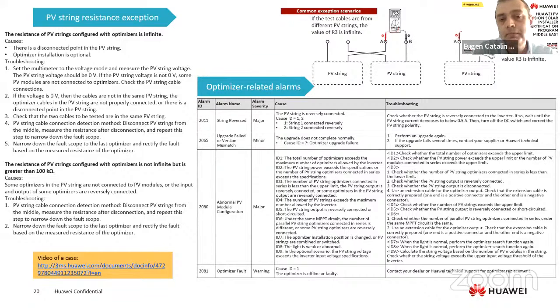We will probably have some upgrade failed alarm, for example. Why is this happening? Sometimes it happens because you set up the inverter in the evening, almost night, when the DC is low, even though the inverter starts the update. It starts because it has power from AC. It will upload the firmware to 80%, and after that, between 80 and 100, it needs DC to finish the update.